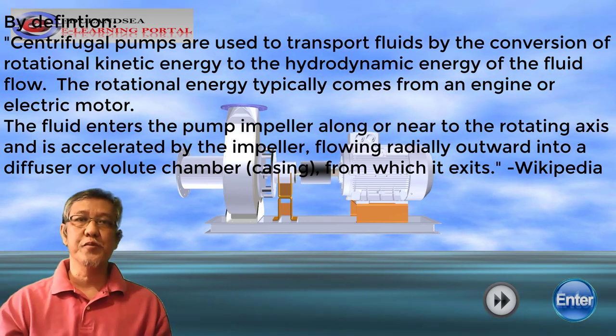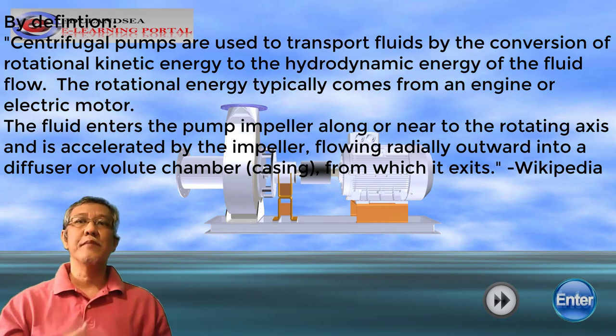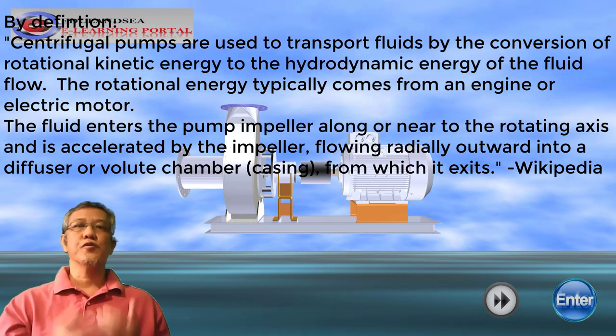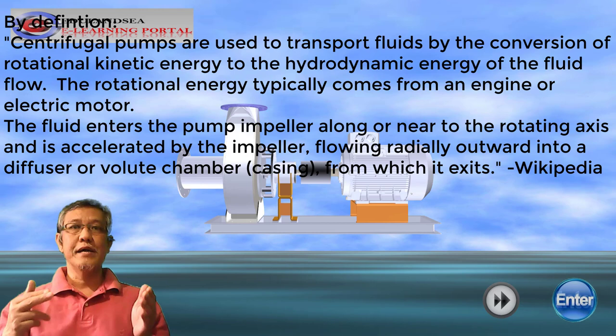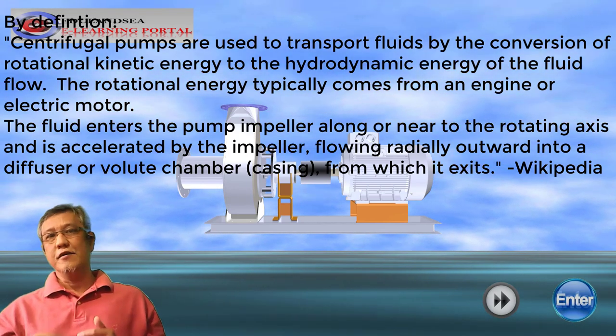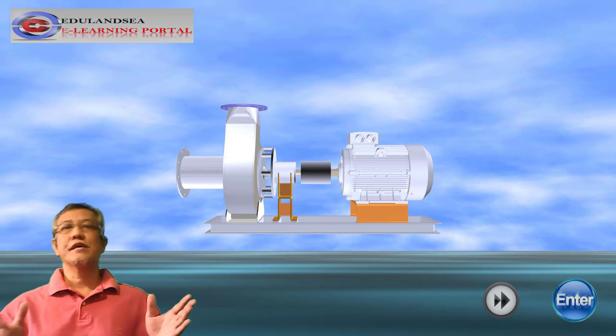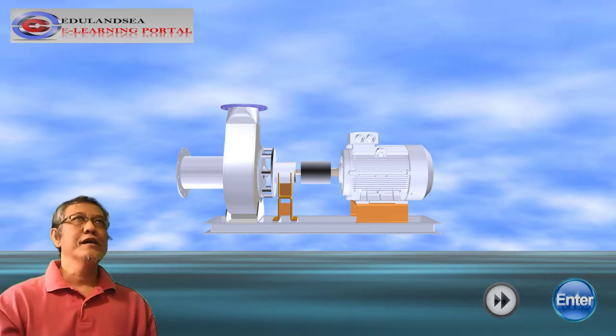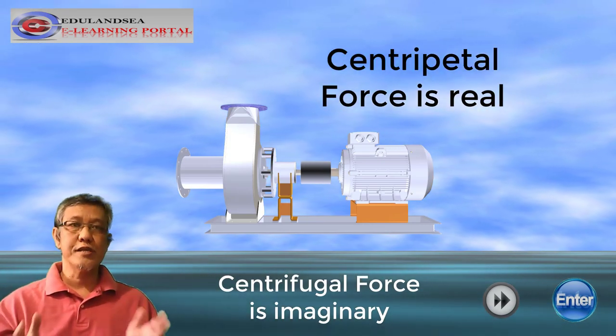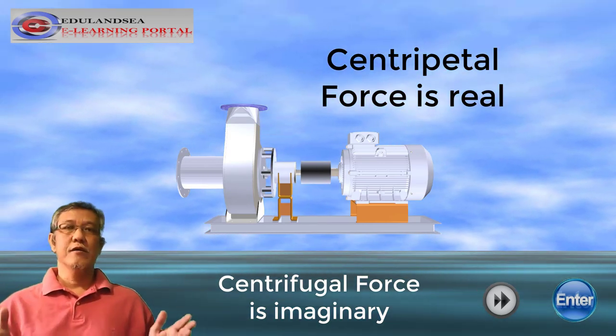By definition, centrifugal pumps are used to transport fluids by the conversion of rotational kinetic energy to the hydrodynamic energy of the fluid flow. The rotational energy typically comes from an engine or electric motor. The fluid enters the pump impeller, and along or near to the rotating axis is accelerated by the impeller, flowing radially outward into a diffuser or volute chamber, or as we call it, casing. In layman's terms, this centrifugal force is actually imaginary — it is the centripetal force that is actually real.